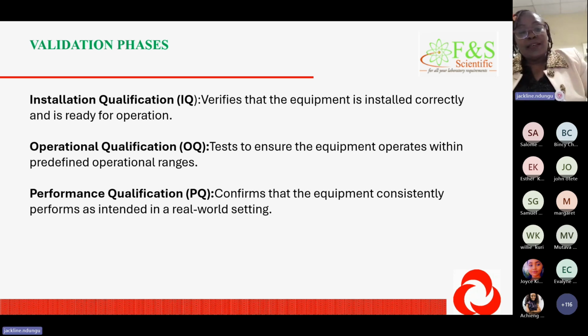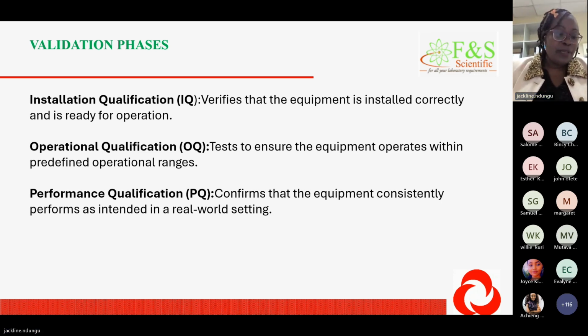Again, I want us to know that once we do these verifications, remember, most of these equipments are not prepared in Africa. They are prepared in Europe or anywhere else. So they'll come here. So we will have to ensure that as we are in Africa with our temperatures, remember some of them are prepared in snow. As it comes here, we need to verify that in Africa it is working correctly. As we do our verification, as we do our reference ranges, we want to ensure that for this population of Africa, our reference ranges are this. But this equipment under these temperatures, it's working appropriately.